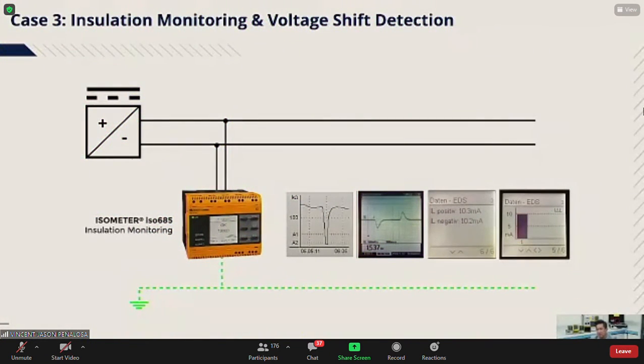Another DC application was using the newer ISO 685. Pretty much what I showed you a while ago, which is the insulation monitoring, or the measurement of insulation. This one will have a few graphs, and it will tell you whether it's on the positive side or negative side. And if it's on AC, it's going to tell you whether it's on line 1, line 2, or line 3. And it will tell you the actual voltage shift to ground. In this case, you have positive, there's a couple of pictures there. Is it on positive or is it on negative? And it's going to tell you the kind of leakage current that you have for that particular line. So it becomes very effective.